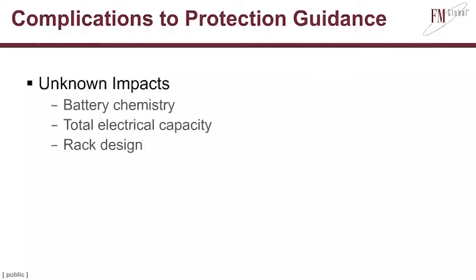For instance, iron phosphate might be less reactive than nickel manganese cobalt oxide. But what happens as the energy capacity starts to get larger is, is an iron phosphate system that's twice the size of an NMC system more or less of a hazard? There's no real understanding of how to compare between those right now. And I can actually go down to an even simpler example.